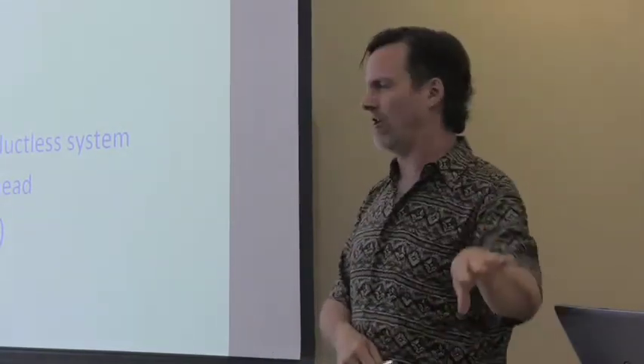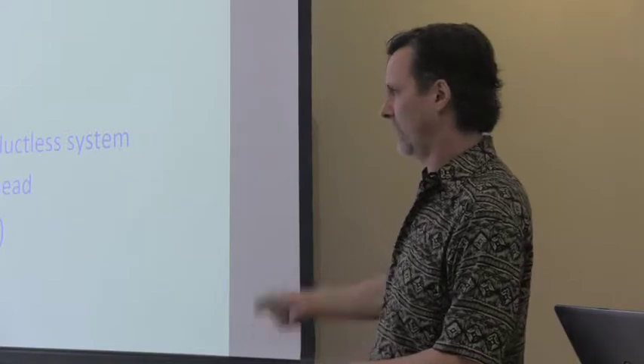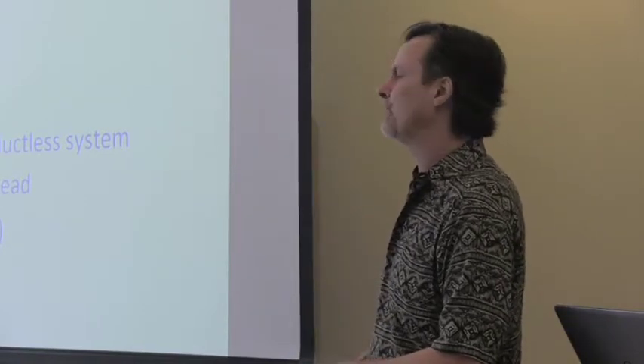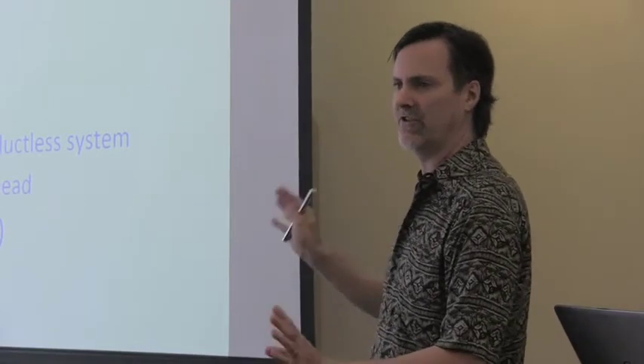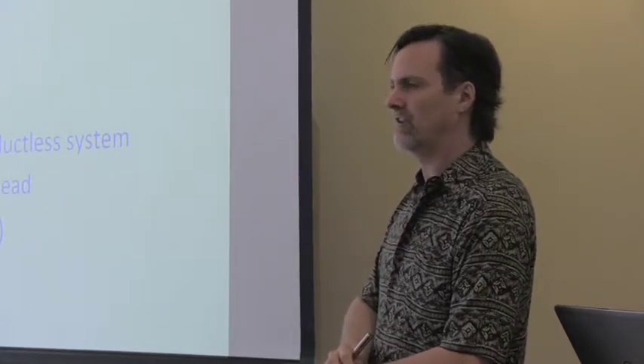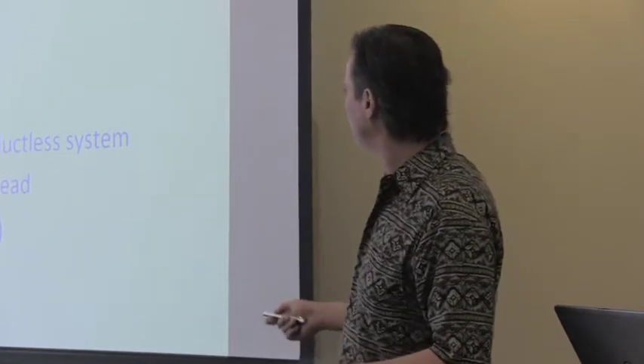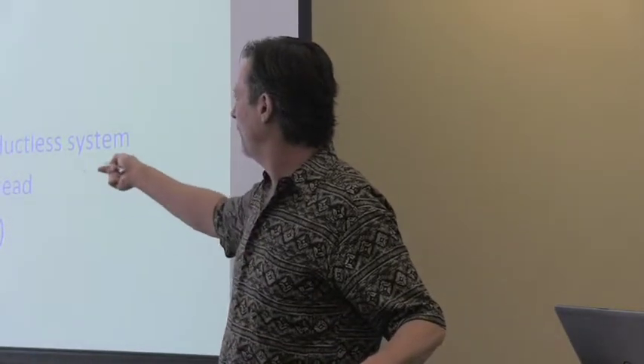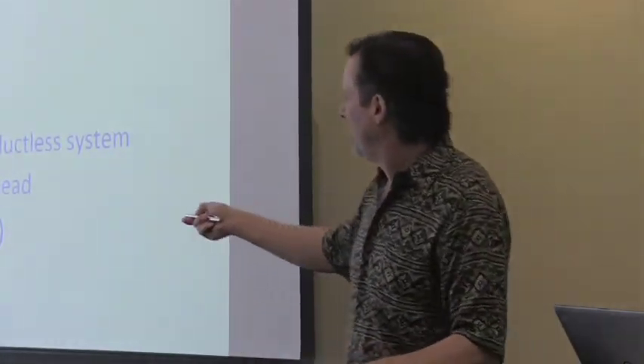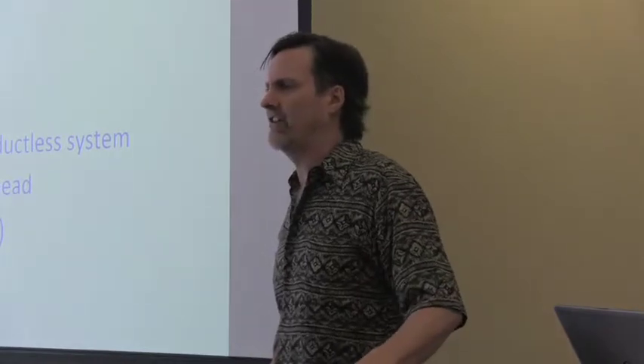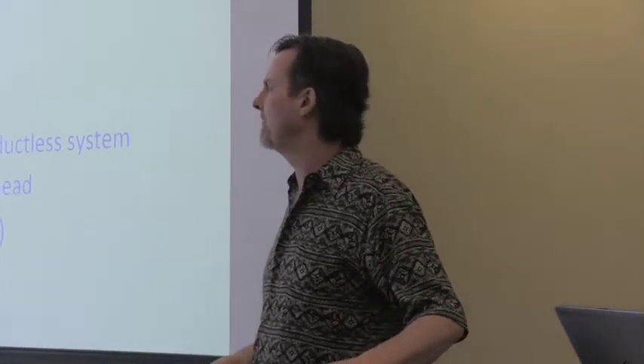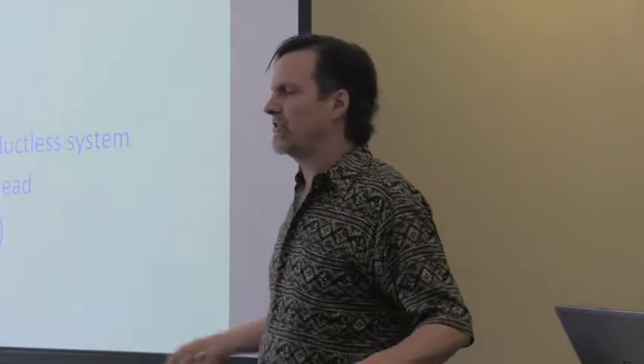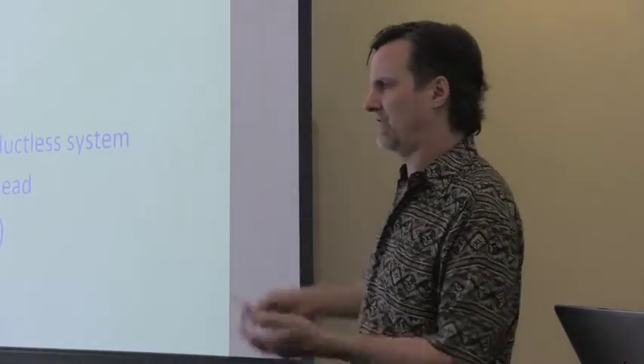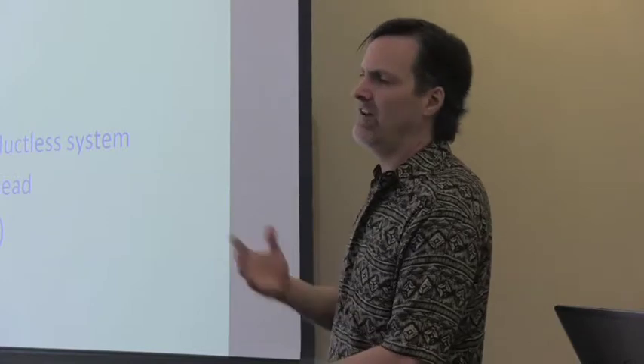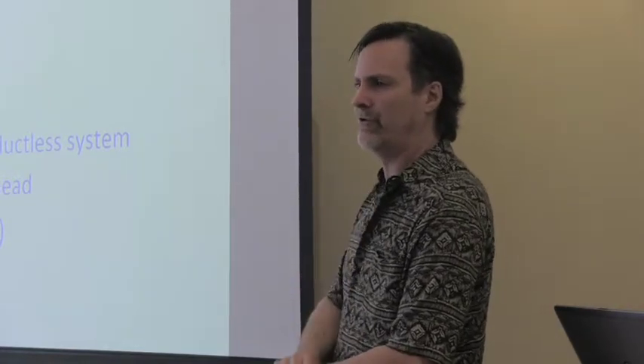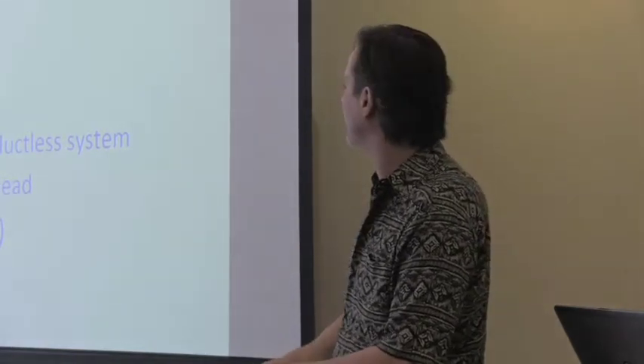You can hide them along baseboards or hide them up above the ceiling, run them through closets from one floor to another. It's much, much easier to get separate zoning so that you can control your heating and cooling at different levels in the house. They're quite affordable. Typically, installed costs somewhere between $3,500 and $5,000 for a single zone system. And in new construction, it's probably closer to the lower end of that because you've got trades in there anyway, and you're not dealing with trying to drill through existing surfaces and patching them up and that sort of thing.